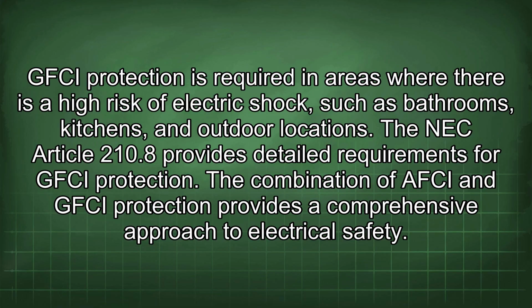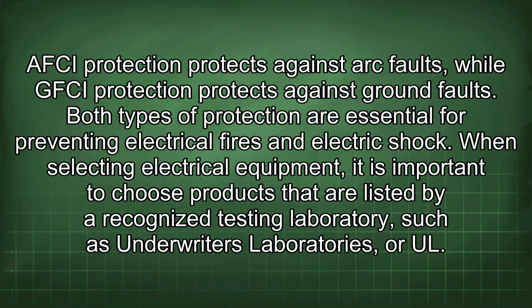The combination of AFCI and GFCI protection provides a comprehensive approach to electrical safety. AFCI protection protects against arc faults, while GFCI protection protects against ground faults. Both types of protection are essential for preventing electrical fires and electric shock. When selecting electrical equipment, it is important to choose products that are listed by a recognized testing laboratory, such as Underwriters Laboratories, or UL.